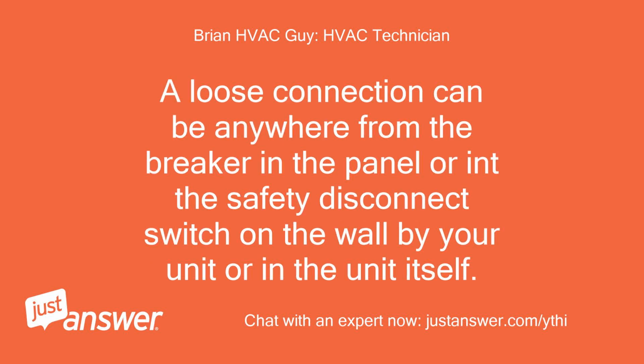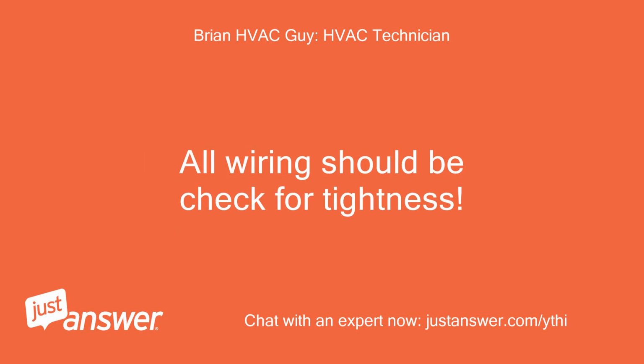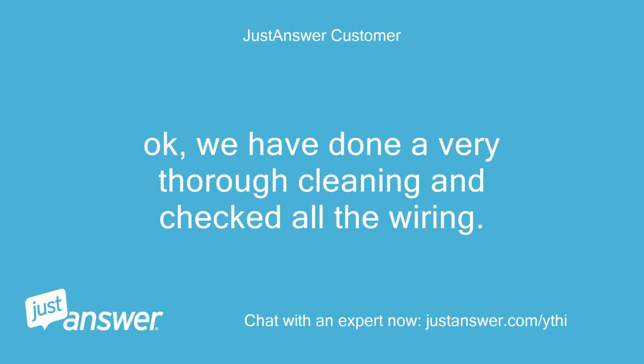A loose connection can be anywhere from the breaker in the panel or in the safety disconnect switch on the wall by your unit or in the unit itself. All wiring should be checked for tightness. Okay, we have done a very thorough cleaning and checked all the wiring.